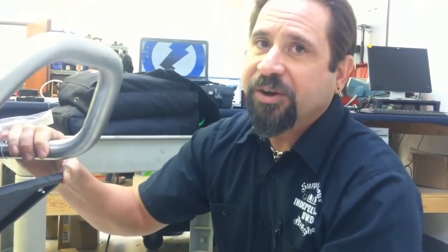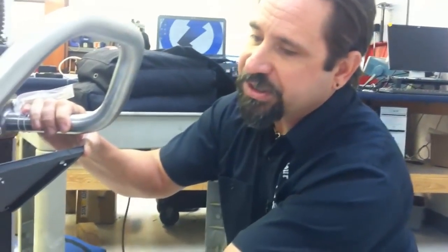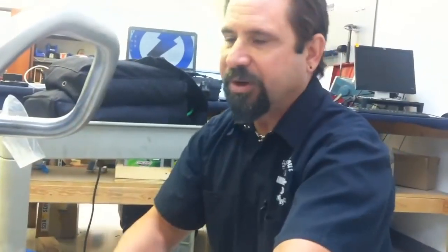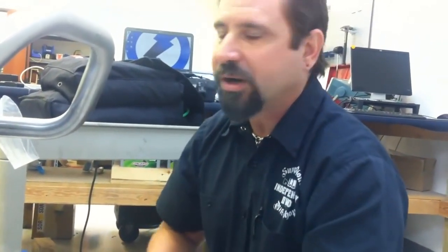I think Megger scores some very high points here by having a detachable cabling system. It lends the ability to remove the cables, which keeps the instrument nice, clean, and ergonomic for loading and unloading to and from a truck, with nothing to get snagged or damaged or destroyed. It also gives a customer the option to have different cabling options. They may invest in a short cable length, or they may invest in a longer cable length. If a cable gets damaged, the thumper stays behind, and just the cable goes off for repair, or a replacement is brought in.